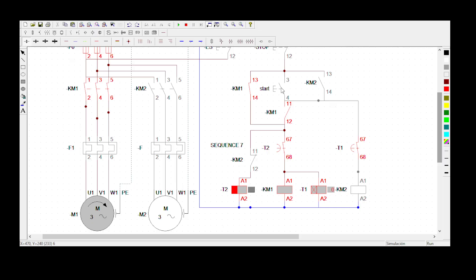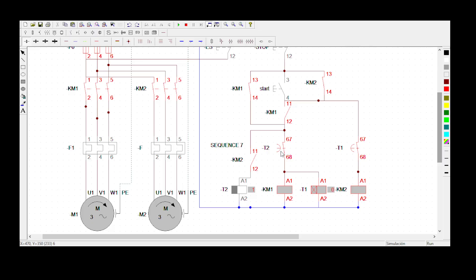I've just pressed the same start button again and KM2 is now energized. When KM2 energizes, its normally closed contact becomes a normally open so that the delay-off timer can start counting. The delay-off timer is counting - it's on one. This normally closed will now become a normally open contact of Timer 2, as you'll see.